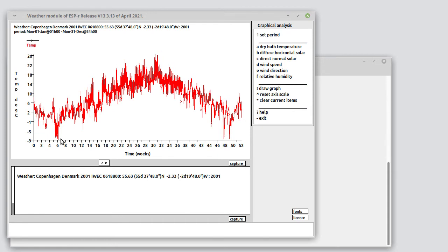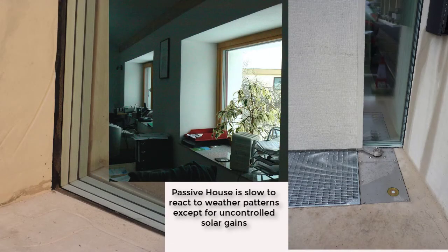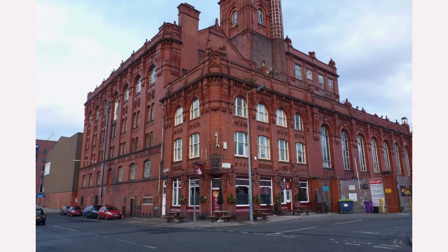A strategic approach might begin by considering how particular building compositions respond to changing boundary conditions. For example, a building approaching passive house standards would respond slowly to ambient temperatures. Indeed, passive house buildings are noted because of how little internal temperatures drift when environmental controls are set back. They're also insensitive to wind speeds and direction, but would be susceptible to overheating if solar access was not well designed. A high mass masonry construction might be less stressed by solar loads, but pose quite a challenge during the Monday morning startup because of the time needed to warm up the mass of the building.